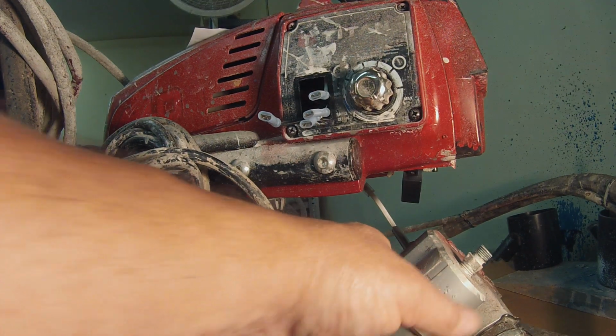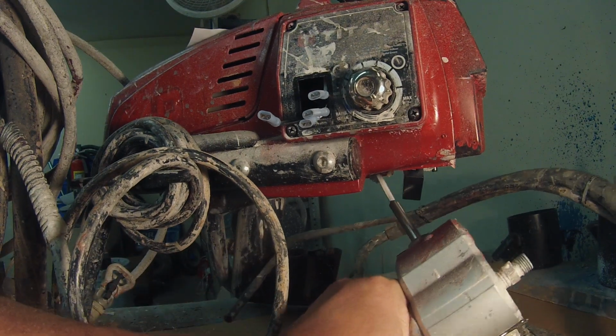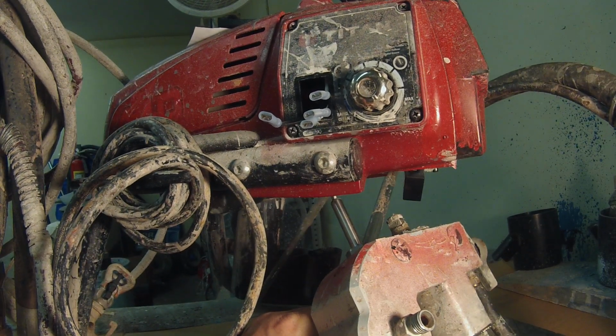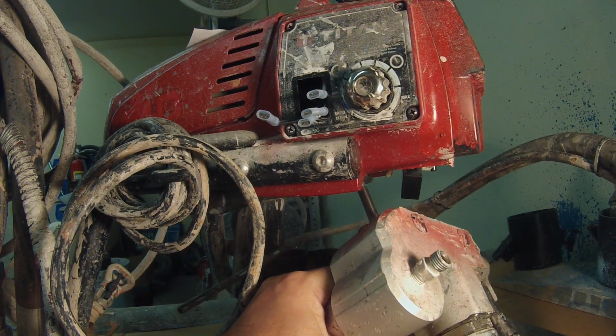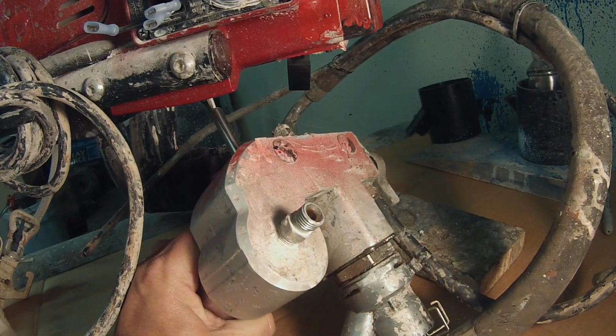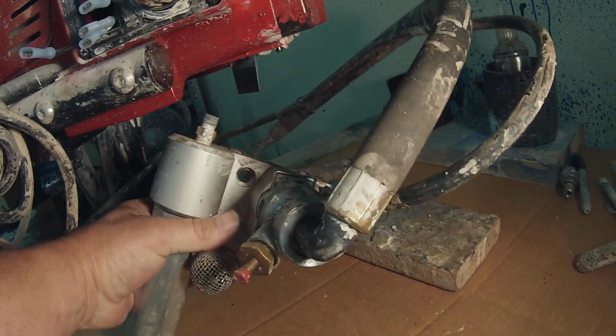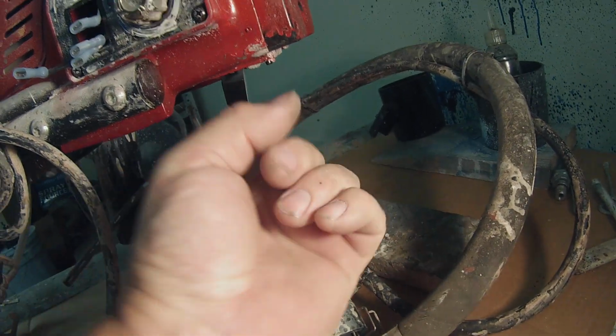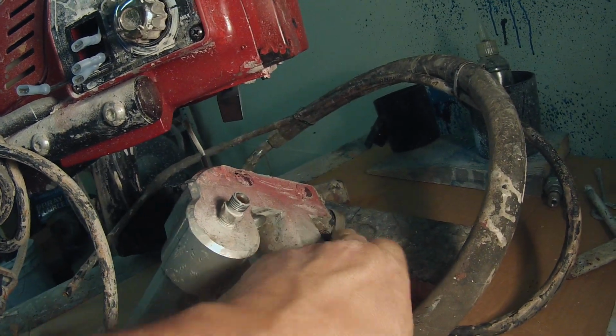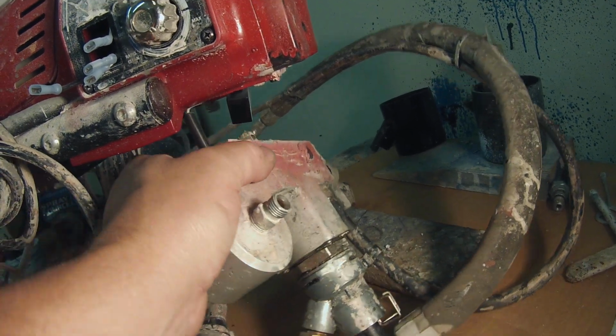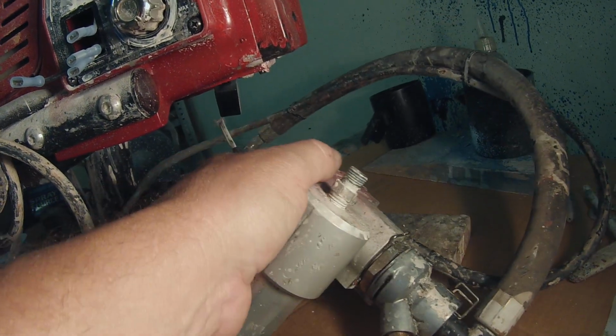So you've got your block right here. This is your pump itself. Okay, that's your pump, and it's bolted on through these holes right here, right to the bottom of the machine. You'll remove the two bolts, and you have to pry down on the block to get it down.